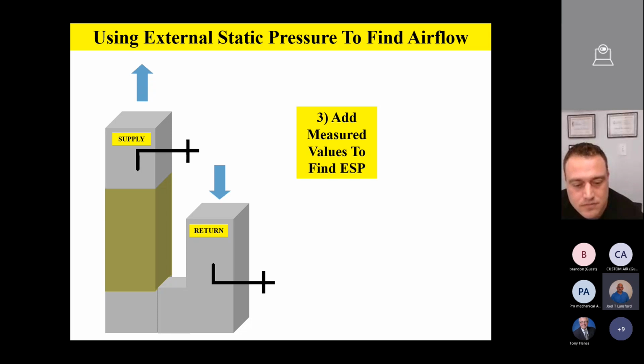That is such an excellent question. So everybody watch my cursor right here. I know it's kind of hard to see my cursor, but if you see my cursor, what you're going to do, let's say this air handler is just sitting on a stand. Well, the fan is going to be inside this air handler. So what we're going to do, we're going to take the static pressure probe and we're going to turn it into the air that's coming into the bottom of the air handler, so what this pressure probe is doing, we're basically reading how much the fan is sucking against that pressure probe. And so that's the idea.